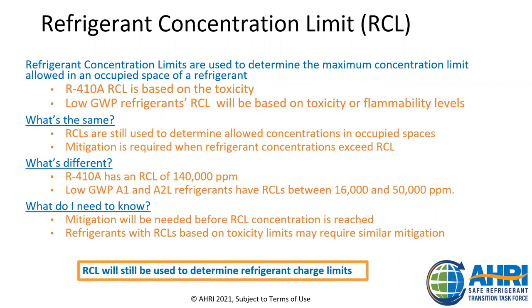What else is the same that I need to think about? Refrigerant concentration limits are used all the time, right? And they're used to determine the maximum concentration limit of refrigerant allowed in a space. R410A RCL, or refrigerant concentration limit, is based on the toxicity. Low GWP refrigerants' RCL will also be based on either the toxicity or the flammability levels. What's the same? RCLs are still going to be used to determine allowed concentrations in occupied space, and mitigation will be required when the refrigerant concentrations exceed the RCL. That's currently the same. What's different?